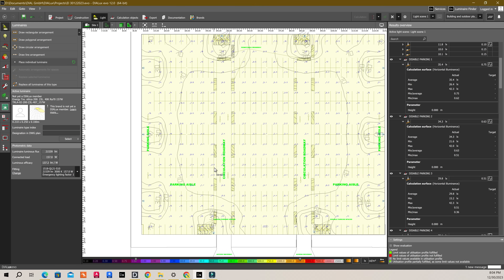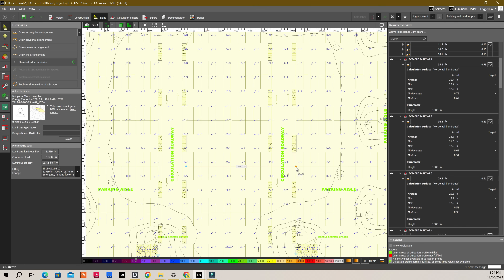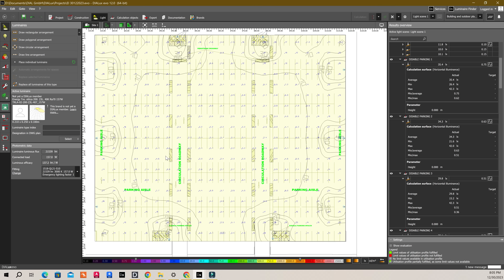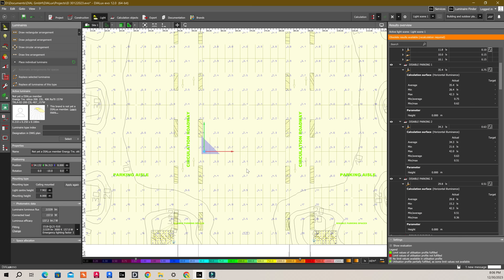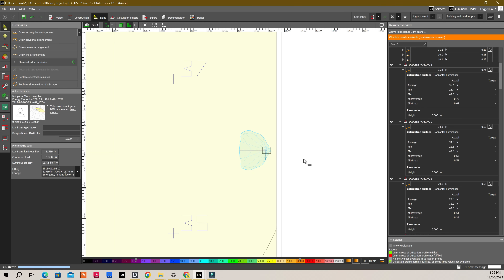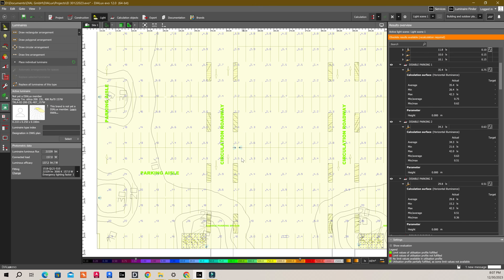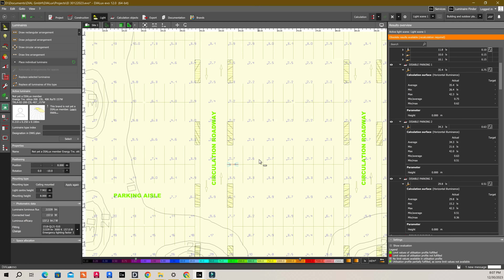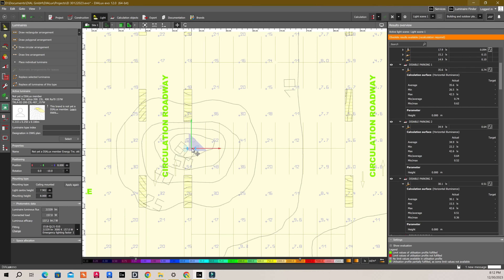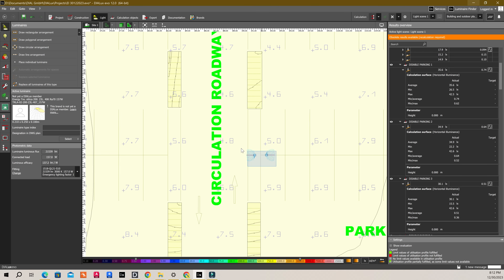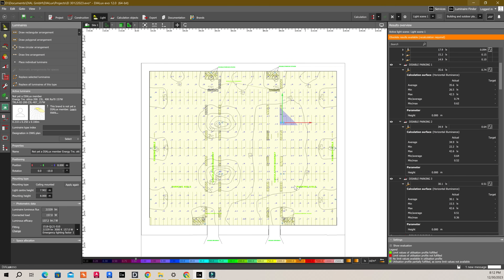I am going to place 4 poles around the center area. Make sure the maximum distance between poles is 50 meters. Each pole will have 2 light fittings facing against each other. Just copy the light fittings we already have in this project — one from the left side and one from the right side — and paste them so that they face against each other from a single pole. Thus, we have 2 light fittings on one pole. Copy the set of 2 light fittings and paste it to the second parking row on the north, and do the same on the right side circulation roadway area as well. So we have got 4 poles at the center area with 2 lights on each pole.